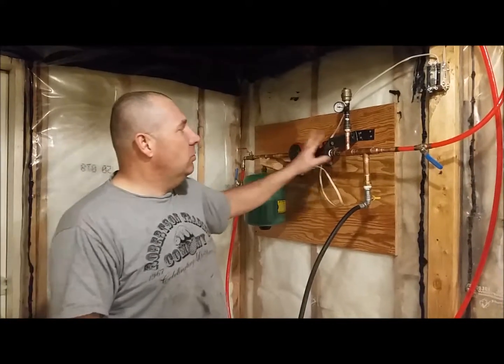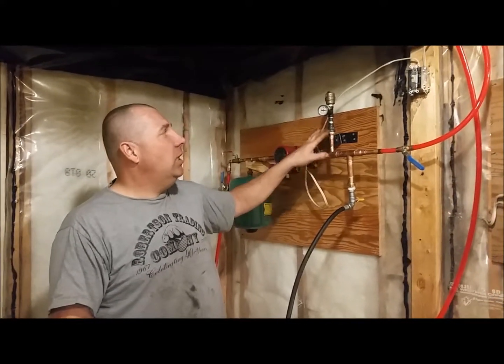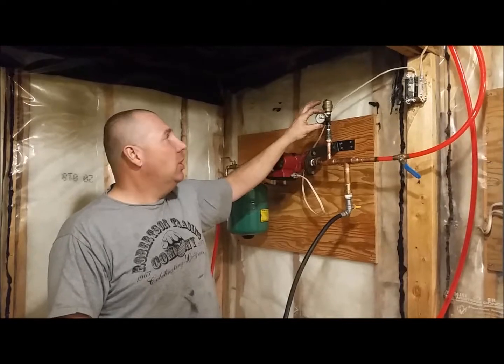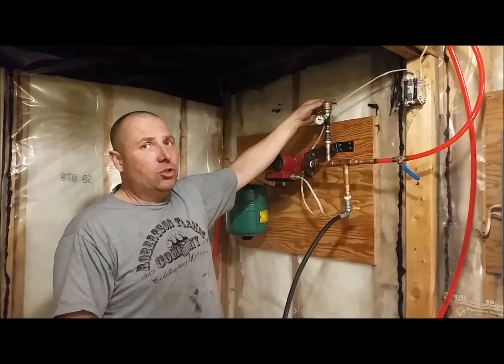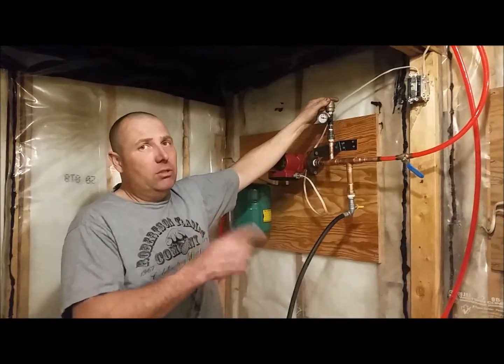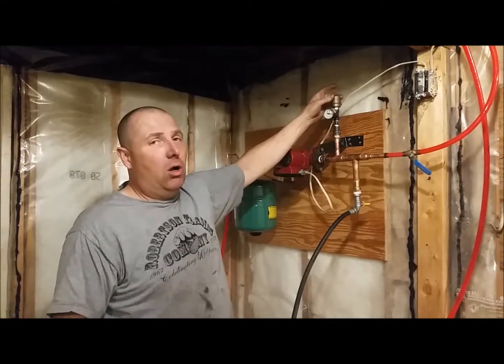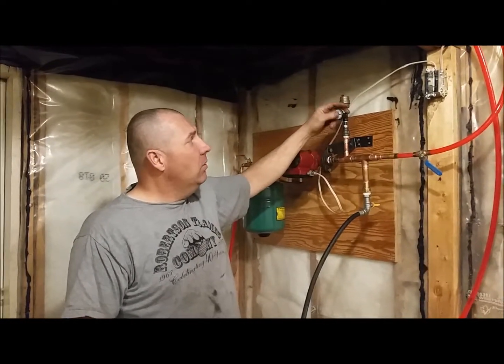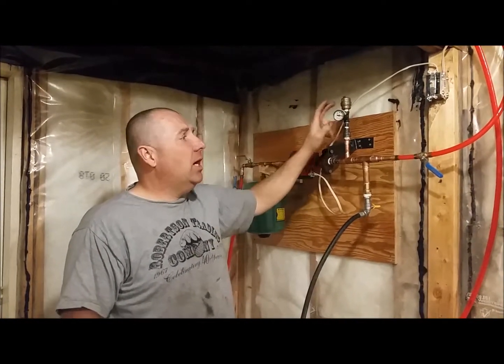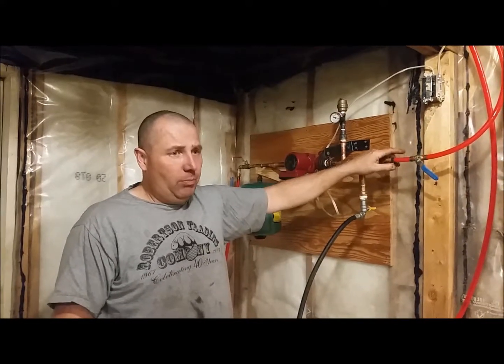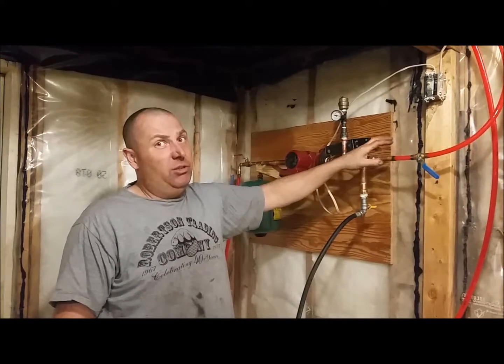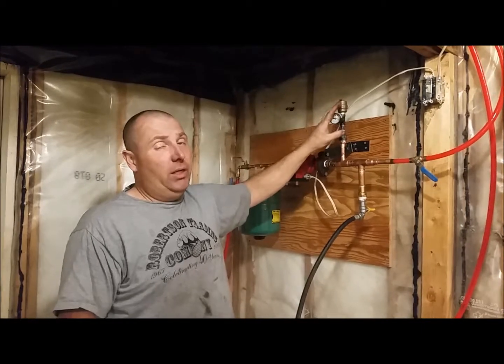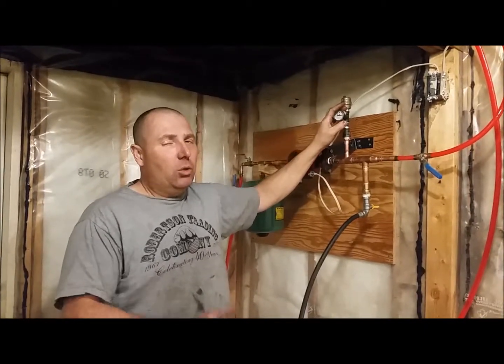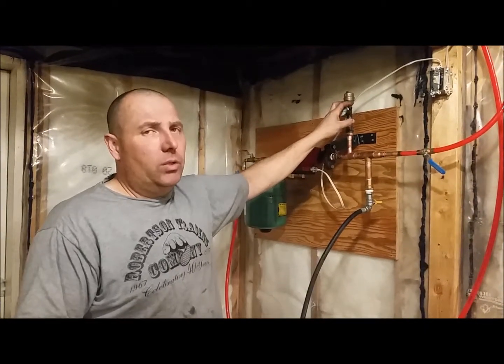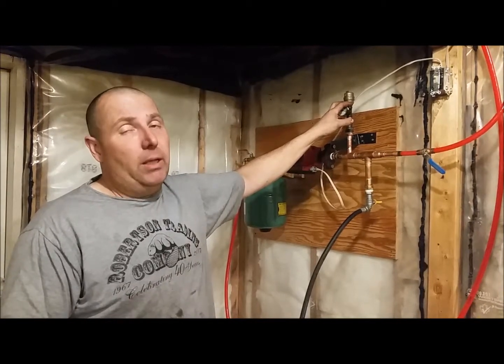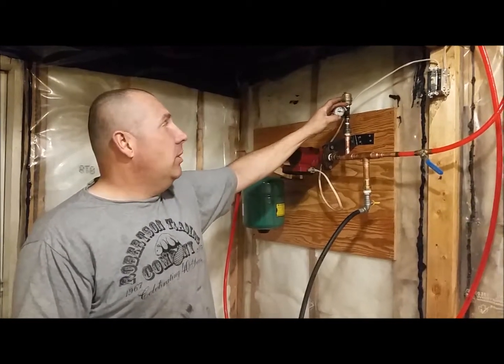So the pump goes through, gives us a T here. This is both a pressure gauge and air trap, which allows any air in the system to be evacuated. It's an auto air trap. Right now we're running at about 6 psi, and the temperature, I believe, is around 8 degrees coming through right here. As the core temperature rises, we're going to get some thermal expansion of the liquids, so our pressure should go up.